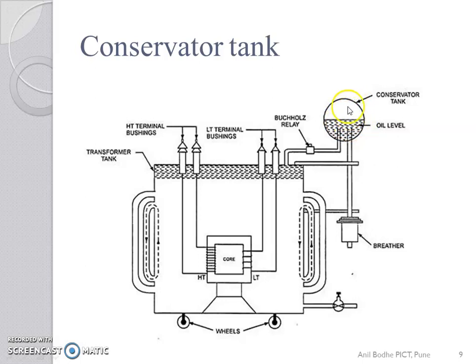Number one, it provides some space for the oil to expand and contract when change of temperature occurs in the transformer. Here please note that during expansion and contraction of oil, the main transformer tank must be fully filled with the oil, and for this purpose the conservator tank of the transformer acts as a reservoir of the oil. And second, it avoids the direct contact of atmospheric air or moisture content with the transformer oil.